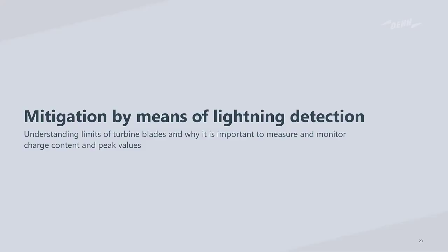Just as a side note, the lightning protection risk assessment standard for wind turbines states that you have to look at each turbine independently within a wind farm, unless they are within a radius of, I think, 300 to 500 meters of each other. Then they can be considered as one between the two, but otherwise you have to consider each turbine separately.